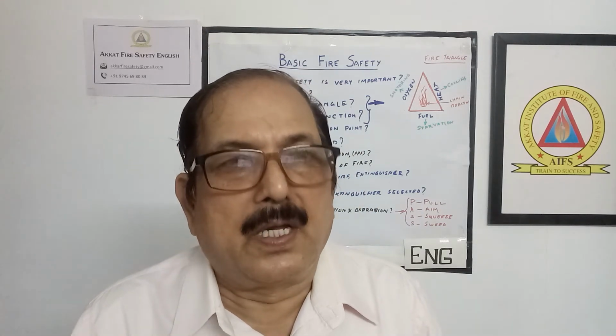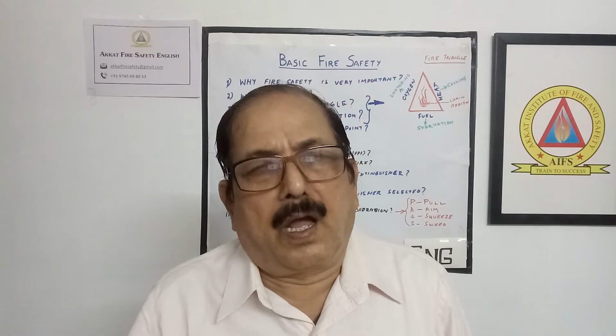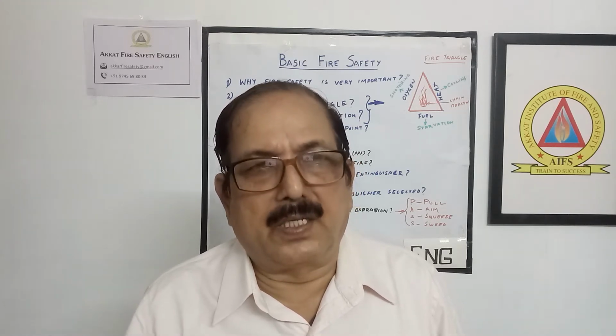Then how are you going to inspect the fire extinguisher? A portable fire extinguisher is not very heavy and can be carried easily from one place to another. We can divide the inspection into three categories. One, a check of the extinguisher before operation. Then every month, at least, we have to do some inspection. Then at least once in 6 months or once in a year, some external agency should come and inspect it.